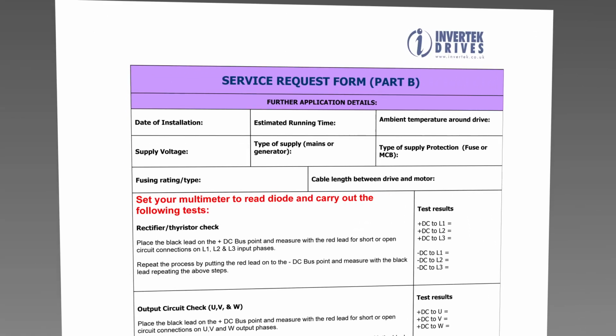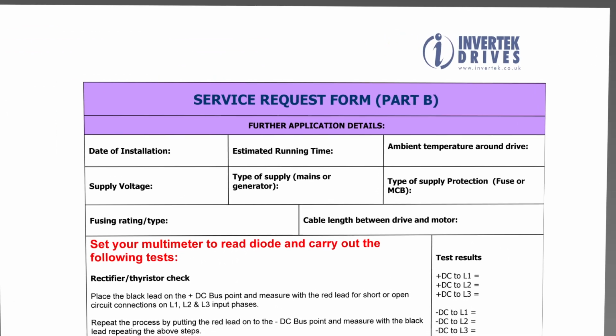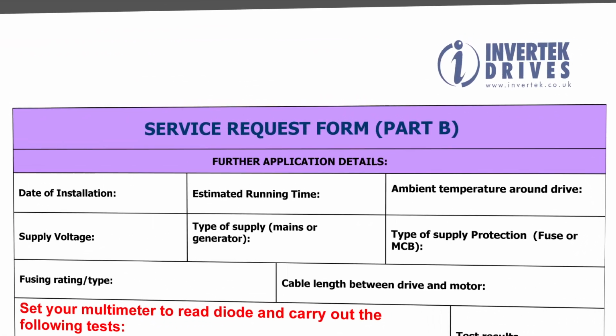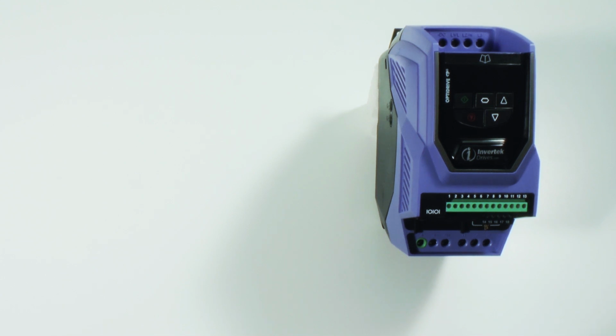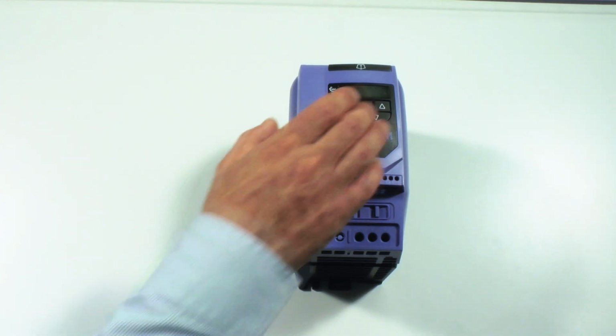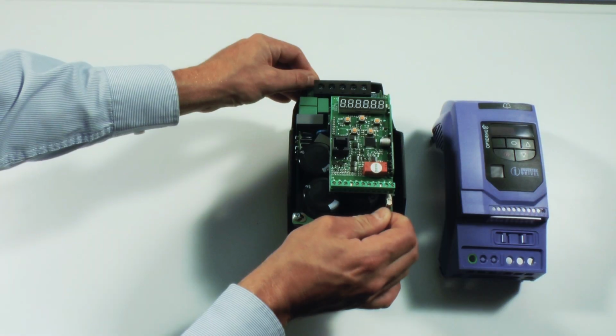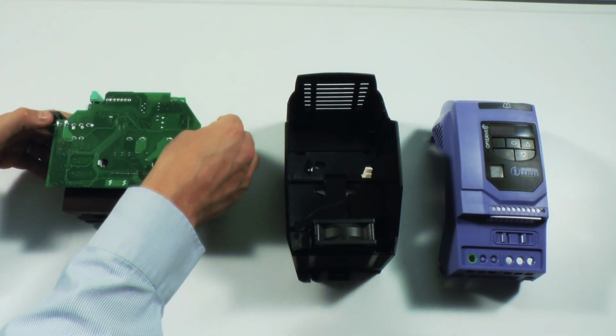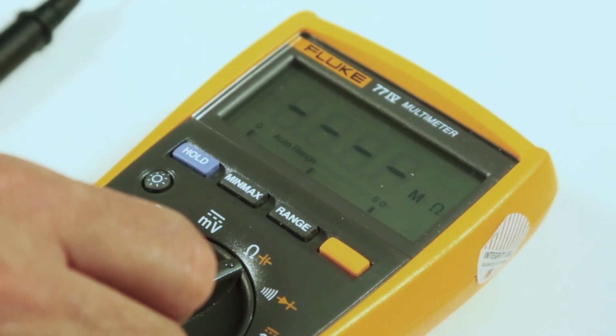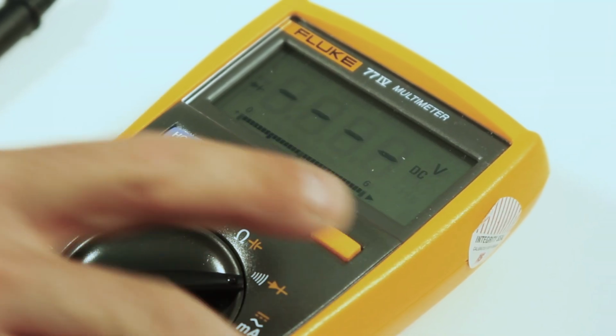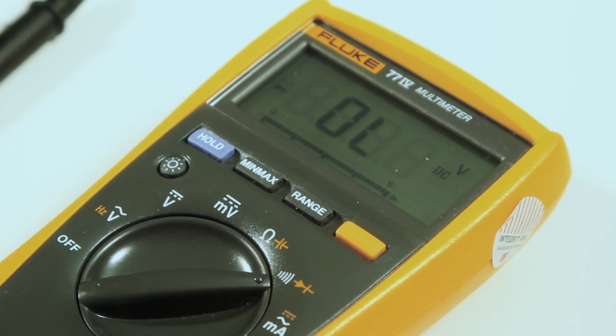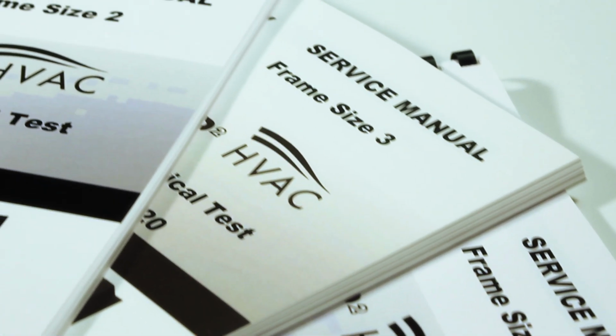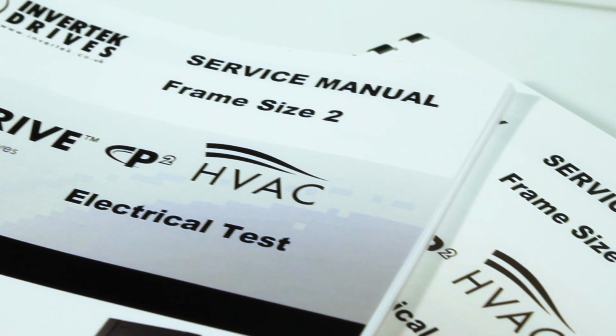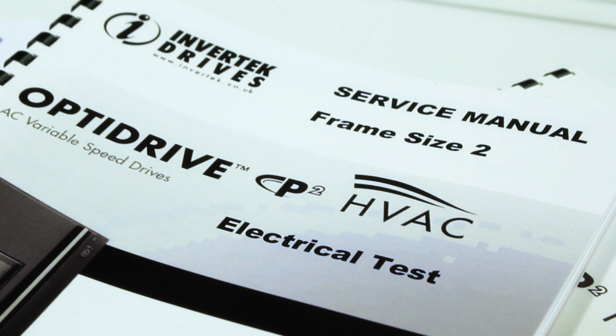To complete Service Request Form Part B, you must now complete the application related information. For the ODP2 HVAC product, the following tests can be completed without disassembling the drive. For the ODE2 product, the cover of the drive will need to be removed. Please refer to the service manual for further information. To begin, set your multimeter to read diode. The same procedure applies to all frame size drives, but will produce different readings depending on the frame sizes. Please refer to the service manual for further information.